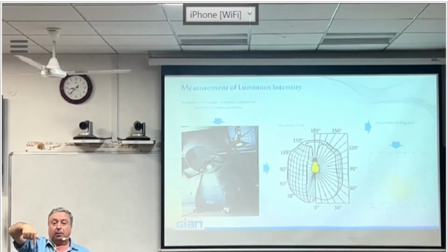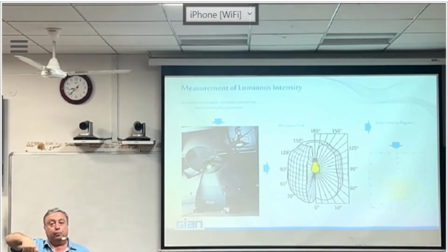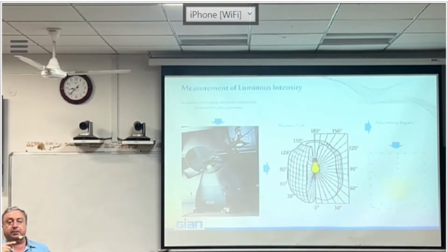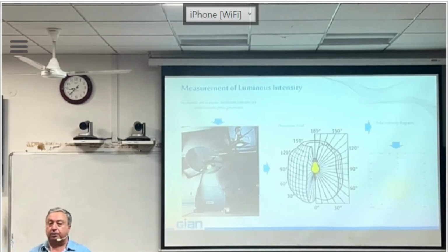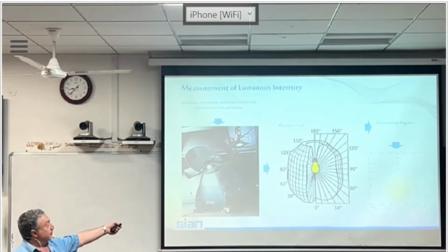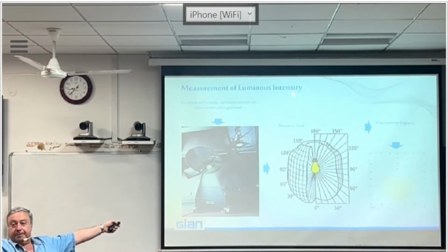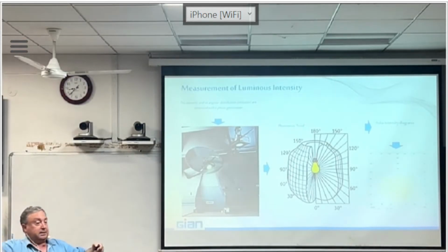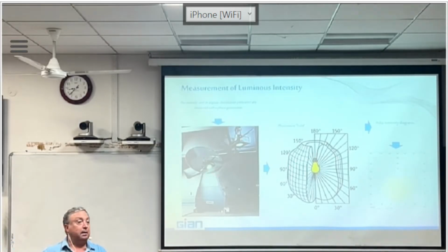always oriented down, and you don't move the lamp, because if you move the lamp, you change the air circulation conditions, and you can change the temperature of the lamp, and you can change its behavior. That means the moving part is a mirror 3 meters further away that sends the light to a calibrated radiometer, and you can scan the system.